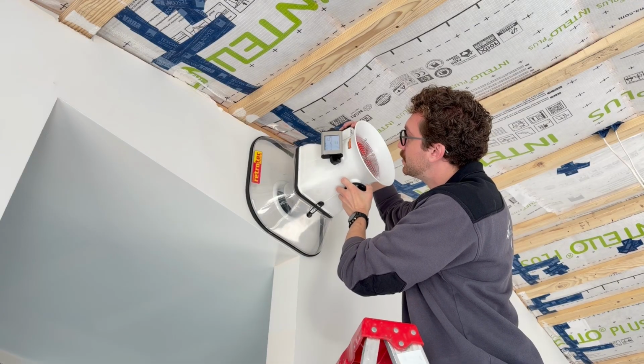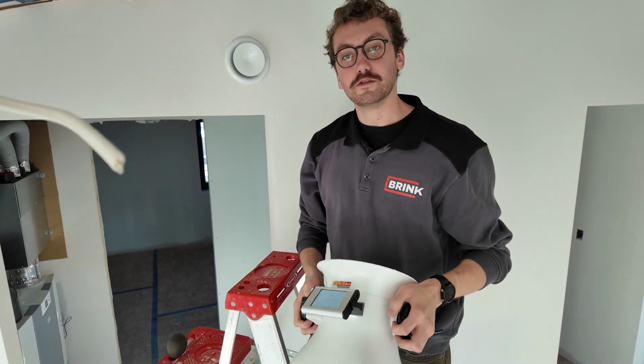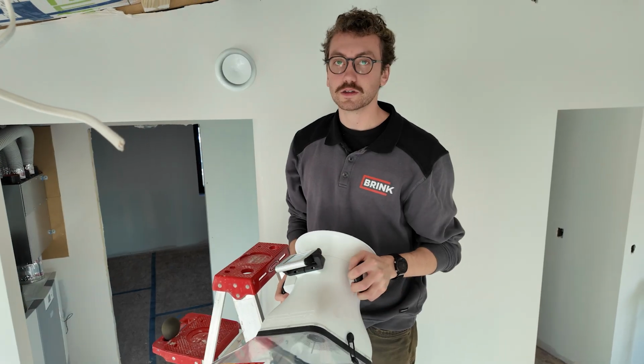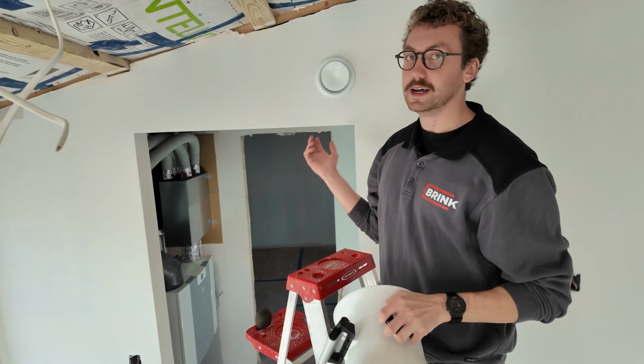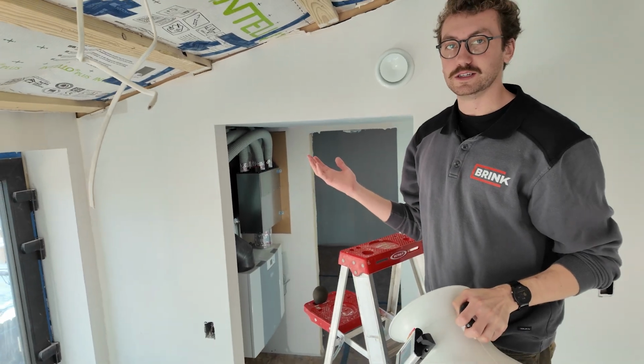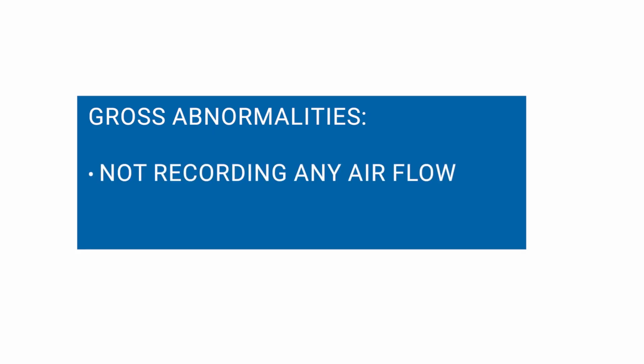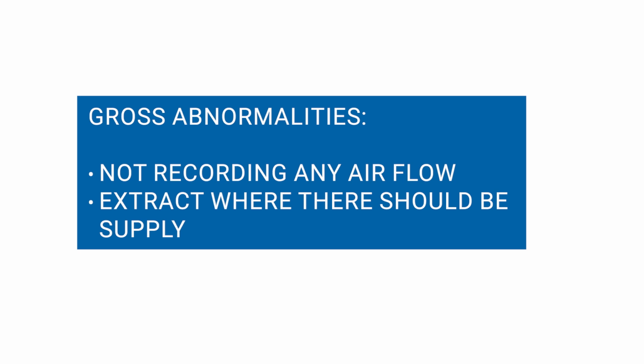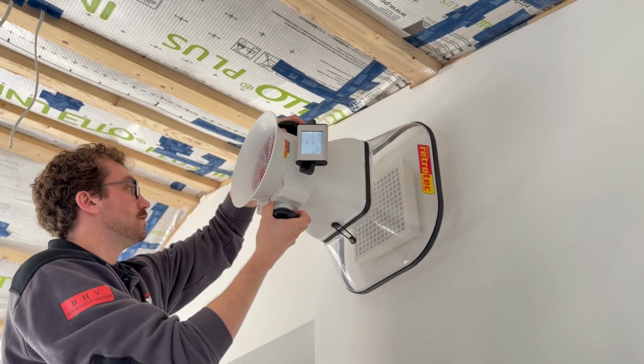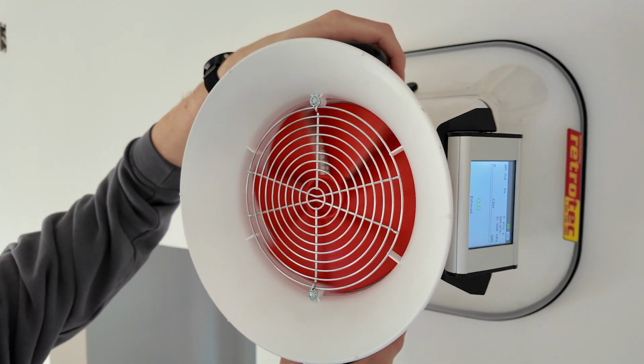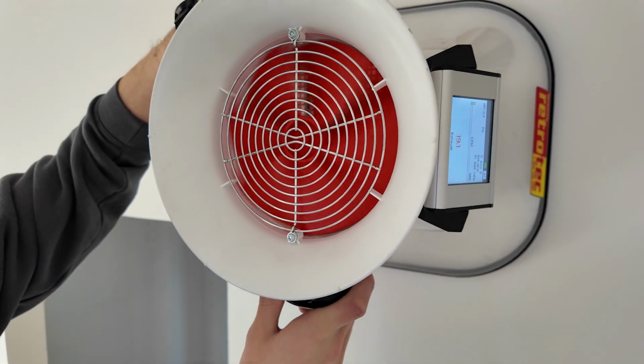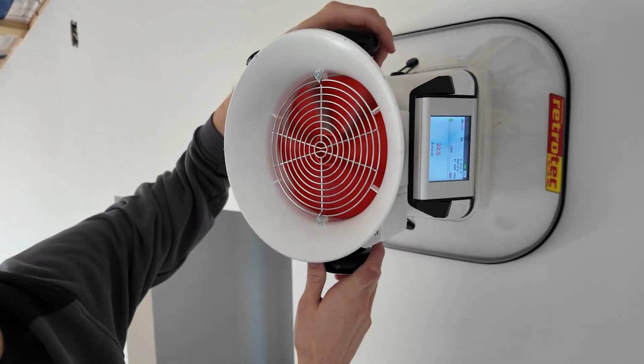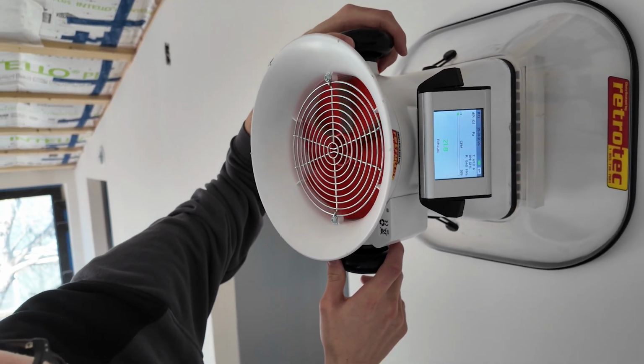And we get up to about 19 CFM. So it's a little bit higher than we want, but that's okay because everything's fully open right now. So as we go and measure the other rooms, we'll probably find that they might be a little bit low. We'll then tighten this one down and everything should balance out and we'll find 15 CFM. If you find gross abnormalities, such as if you are not recording any airflow, or if you are finding extract where there should be supply, the ductwork should be addressed before continuing. Once all flow rates have been recorded, identify which diffusers are supplying or extracting more air than is designed. If no gross outstanding issues are found, then fine-tune adjustments can begin.